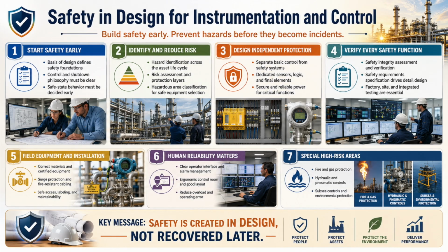Pressure, flow, level, temperature, and process analysis systems need correct materials, pressure ratings, isolation, flushing, purging, sealing, drainage, and maintenance access. Thermowell strength and vibration calculations are essential because a failed thermowell can become both a projectile and a process release path. Process analysis systems must control sample pressure, temperature, transport delay, calibration gas, disposal route, return route, venting, and hazardous area impact. Cables are part of the safety function.